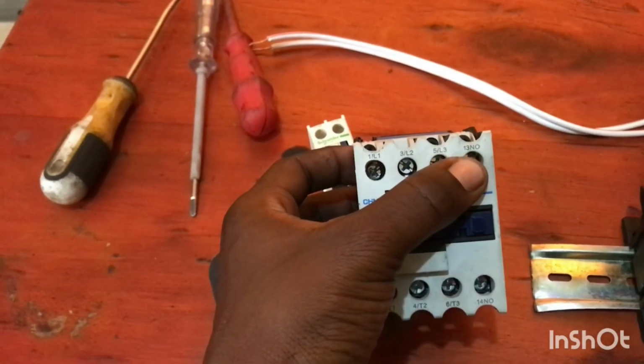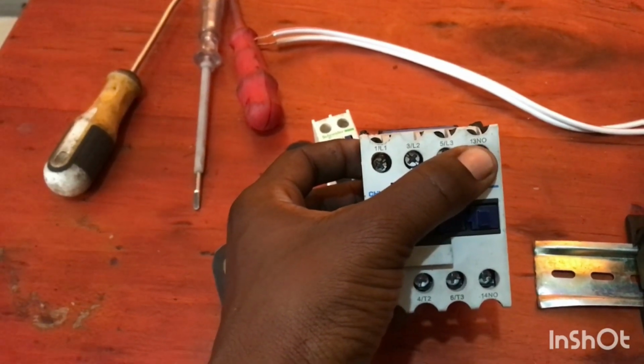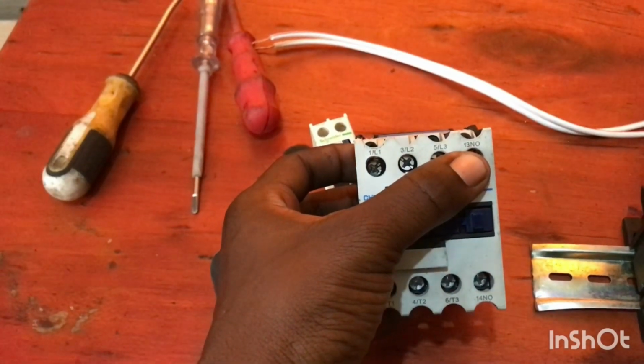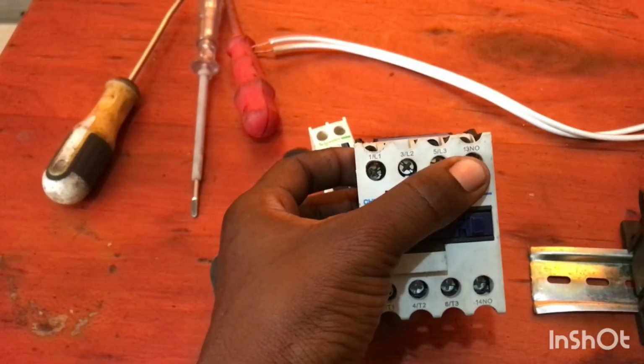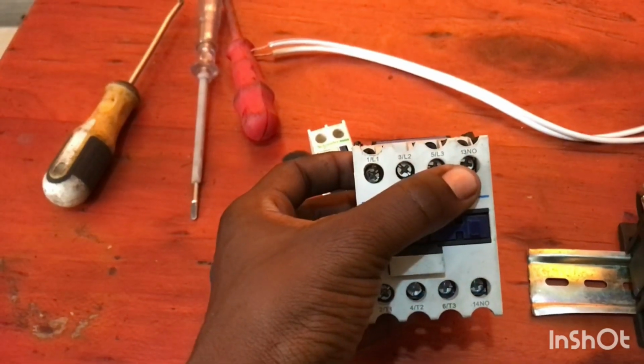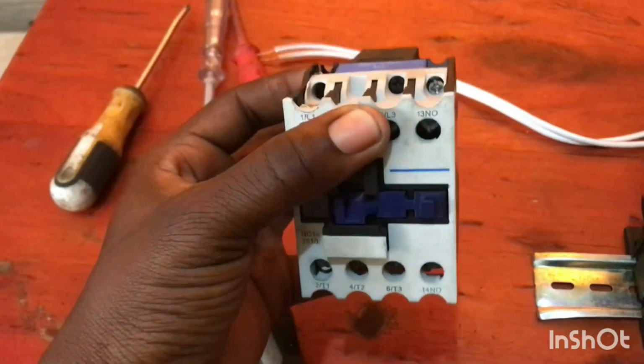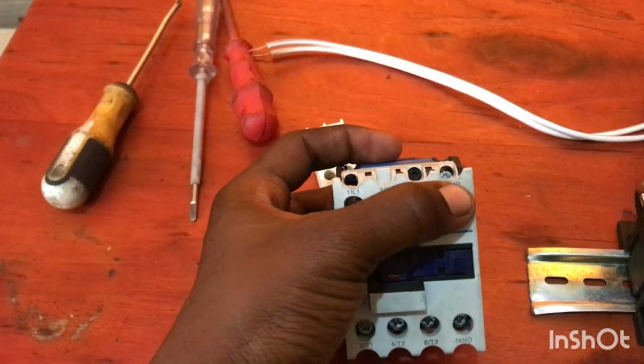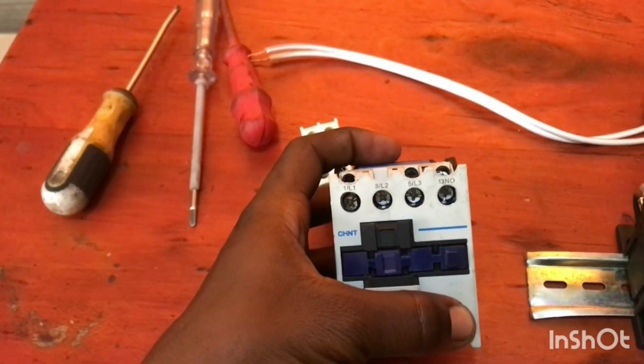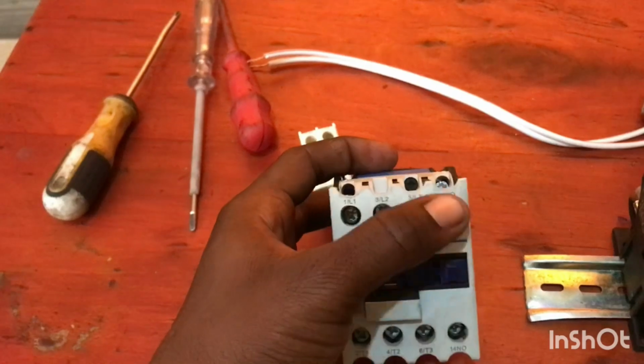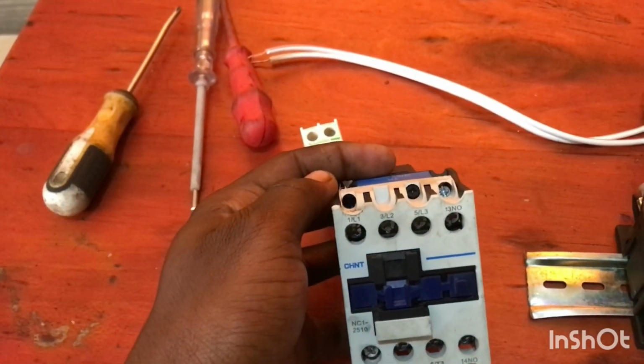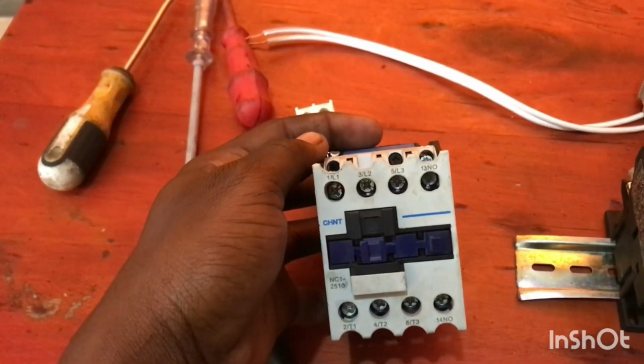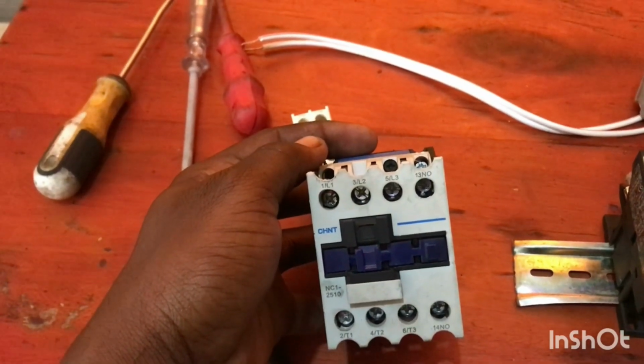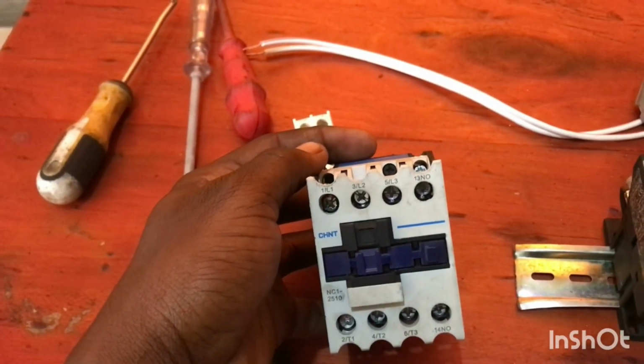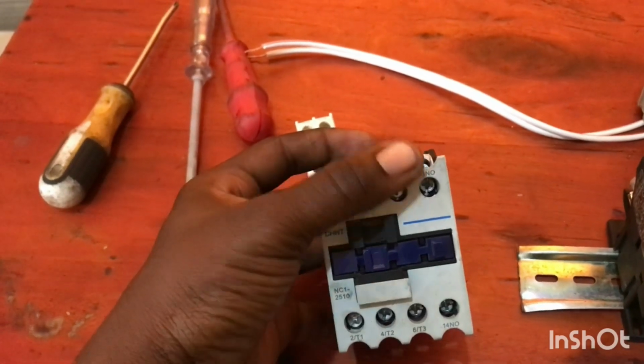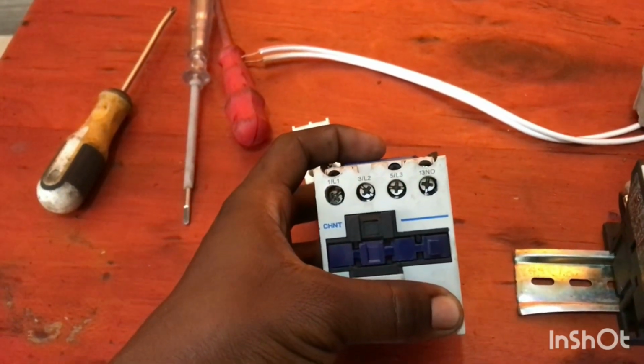So normally open means that when this contactor is not energized, like the way it is here, where we have not connected anything to it, it is not energized, it is at rest. So, for the normally open, between point A and point B, these two contacts, there is no power because it is open. But normally closed means that when the contactor is at rest, there is power from point A to point B.